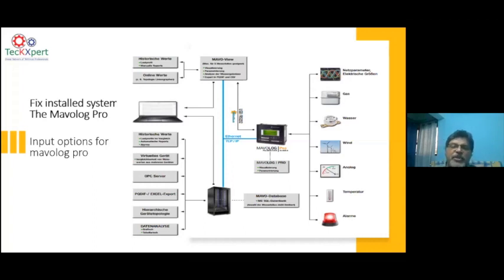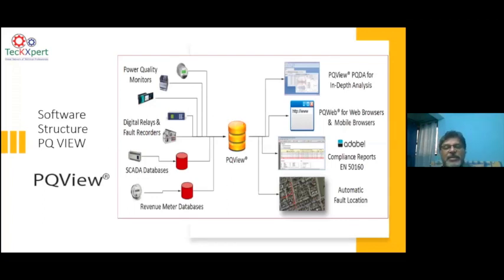But if you have a recording happening through a PQ meter, from the waveform we can always see that there is a distortion in the voltage. That means the OLTC is not functioning properly. So before the OLTC fails, we can find out the performance of the OLTC by continuous waveform recording. There is also something very important when it comes to grid-level monitoring, a software called PQView, which I have been familiar with, and I've been doing these sorts of projects abroad. PQView is database software. In the software, you can bring in data from your power quality monitors, your protection relays, your SCADA system and your revenue meters, and you can analyze all the data and create the required reports or waveform analysis. For example, if an event takes place, the event data can be captured from the digital relays or from the PQ meter, and by doing this, you can relate a power quality problem to any other event.